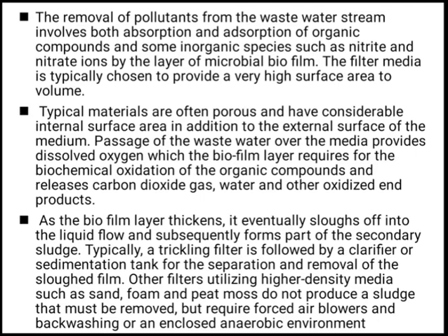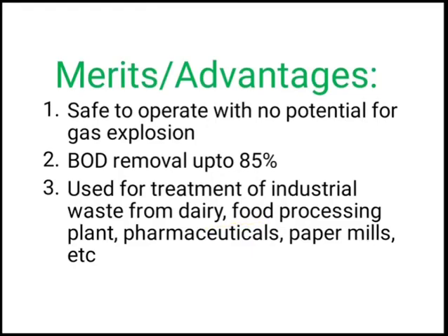The filter media is typically chosen to provide a very high surface area to volume, and in this way we can remove the sewage and purify the water using the trickling filter method. There are advantages, and obviously some disadvantages. The trickling filter method's advantages are that this method is very safe to operate, with no potential for gas explosion.